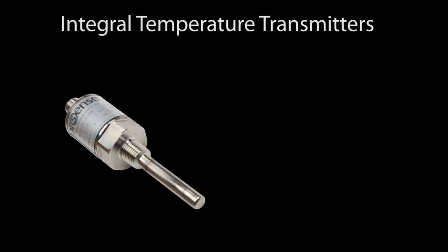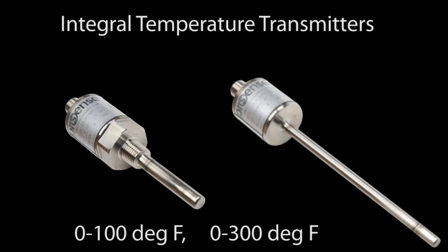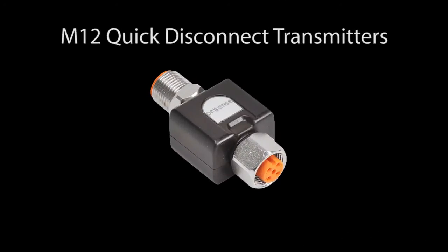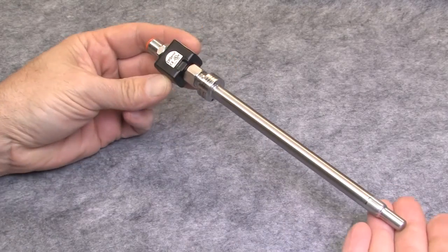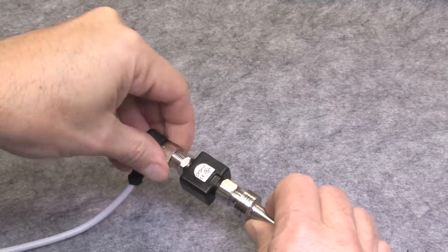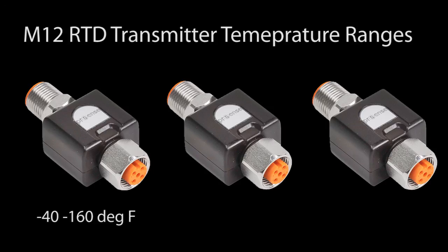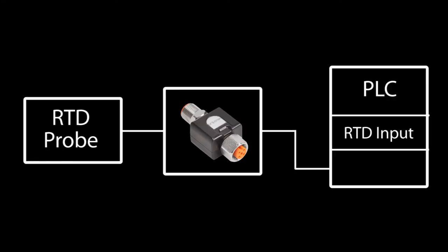The integral temperature transmitters come in several temperature ranges with quarter-inch NPT threads so you can screw them right into a process tank, or with a straight shaft that you insert into a compression fitting. These integral sensors are handy because everything you need is in one package, though they don't have as many temperature range offerings and are only available as RTD sensors. The M12 transmitter is for 3 and 4-wire RTD probes — you just plug it onto the probe and instantly have a 4 to 20 milliamp temperature transmitter that works with any M12 4-pin cable. You can also use an M12 extension cable between the sensor and the transmitter, and you must specify the fixed temperature range you want to use.